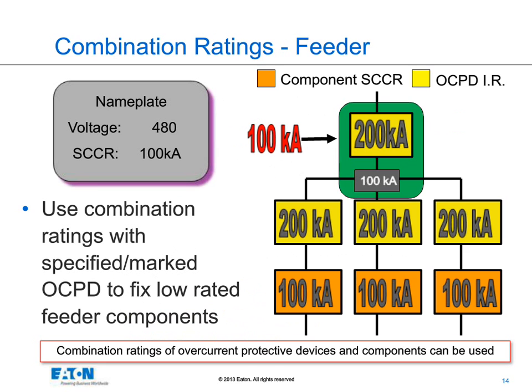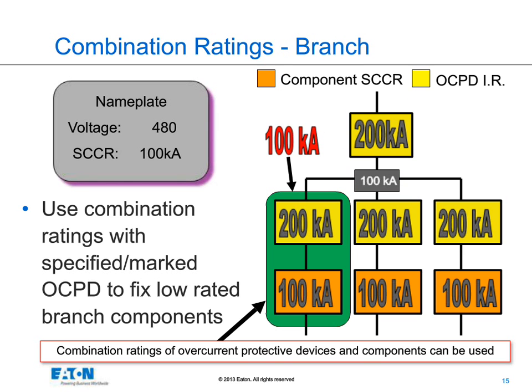Here's an example of how to apply combination ratings in the feeder. Bussmann offers power distribution blocks with high SCCR when protected by a specific type of fuse. In this instance, we might have a high SCCR PDB provided we have a specific ampacity and class of fuse ahead of it, and that combination would become 100KA. Similarly in the branch — perhaps a contactor or motor starter — the manufacturer has tested that component with a specific overcurrent device, and the combination of that overcurrent device and the component is good for 100KA.